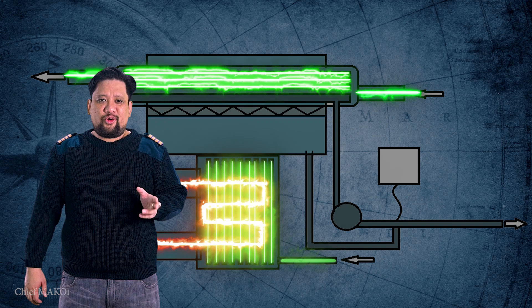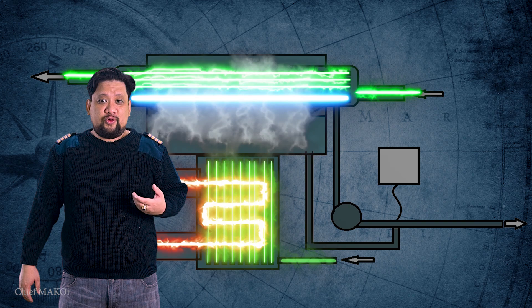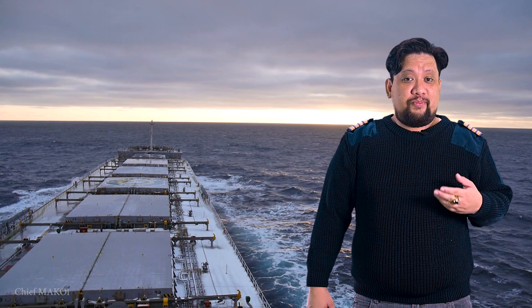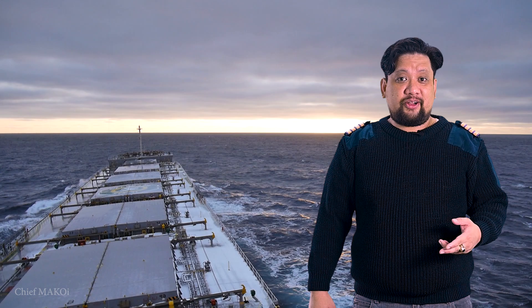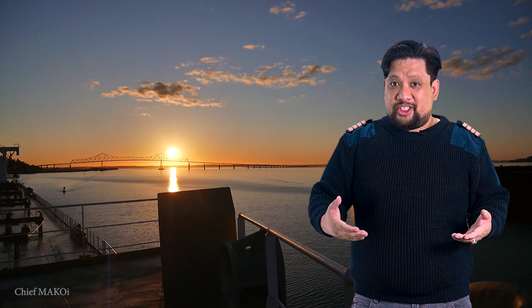For us to fully understand how the distillation plant works, we need to dive into a few more details and learn the function of each major component and see how the fluid reacts when passing through each of them. For optimal performance, distillation plants are used when the ship is underway — that is to say, when the main engine is running at navigation speed. This is mainly because the seawater is cleaner in the deep and open sea as compared to near land. Also, the heating medium used by the evaporator to boil the seawater comes from the main engine jacket water, which has a temperature of around 80 to 85 degrees Celsius.